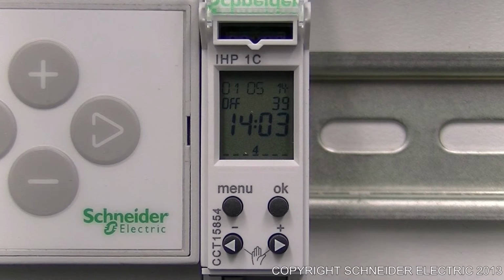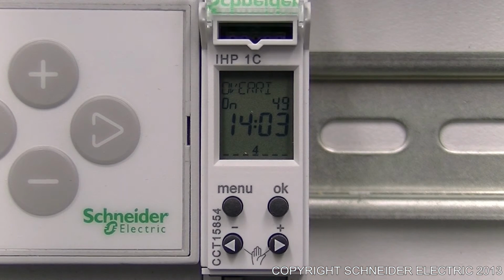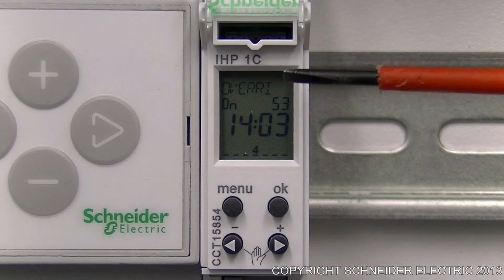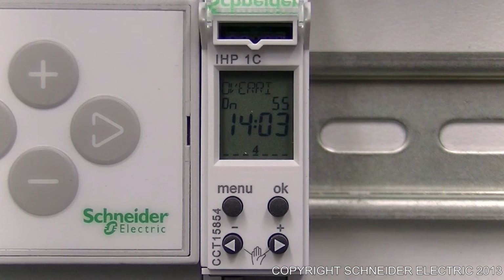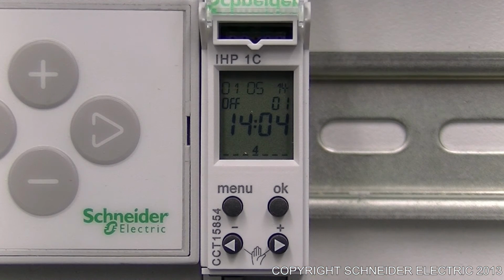There is another way of quickly engaging overrides as well as permanent overrides. The way we go about doing that is if you press both of the arrows together for a couple of seconds, it will override the output to on. And you can see that we've got on and override up the top. To cancel it, you just press those two buttons quickly, like just a short press, and it's cancelled it.